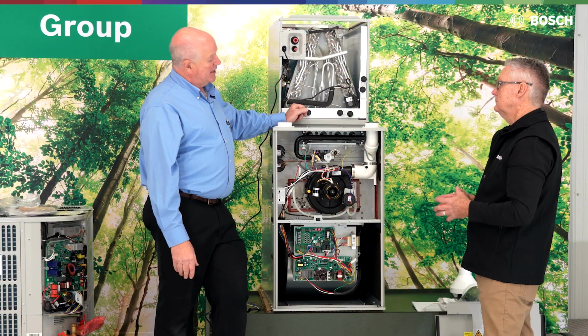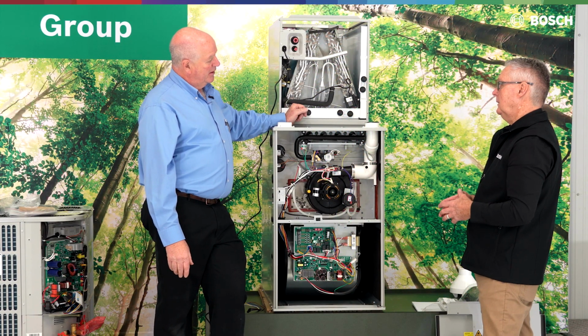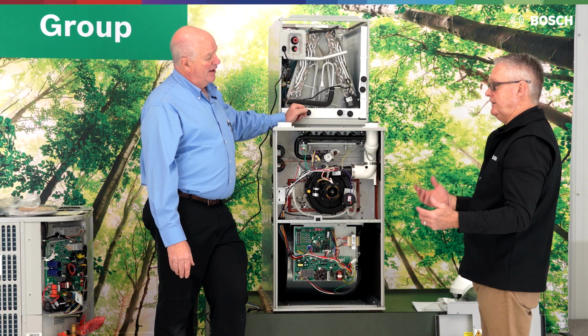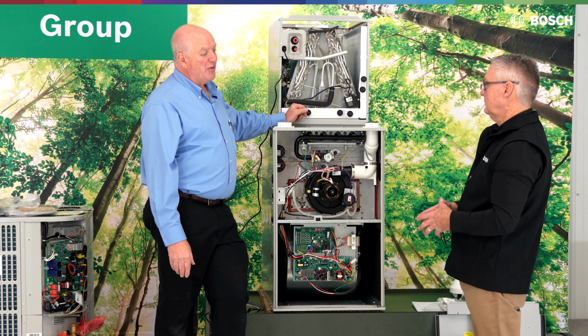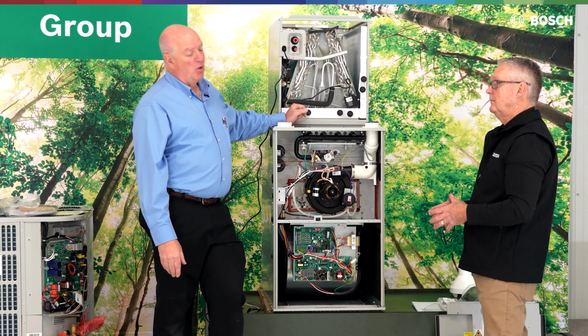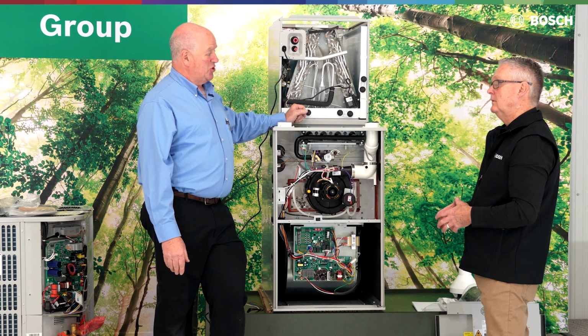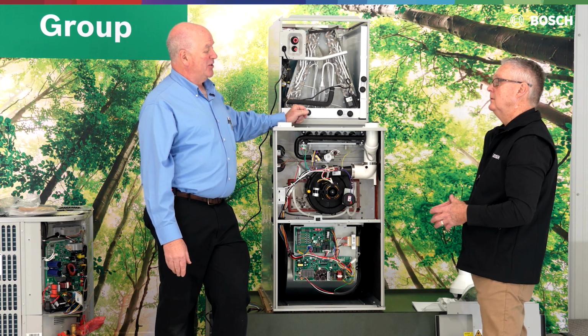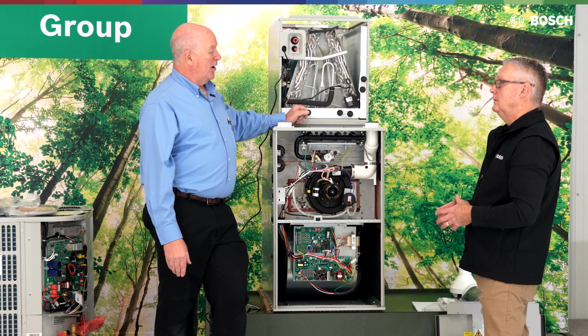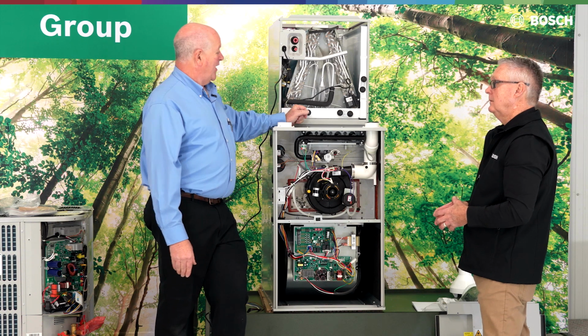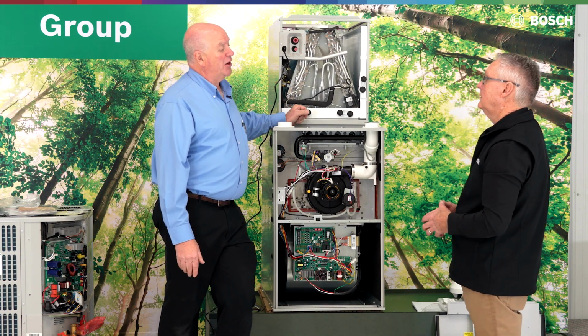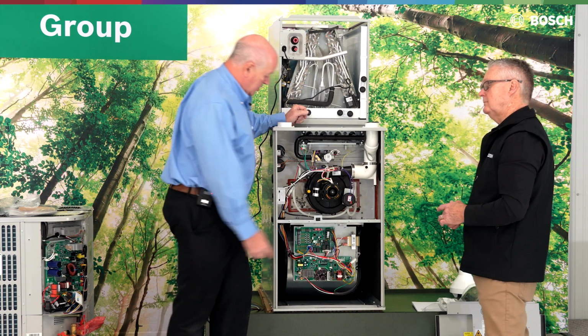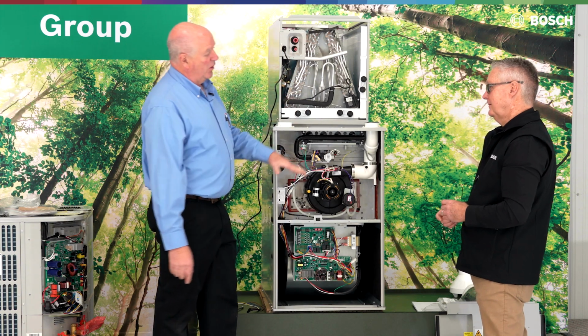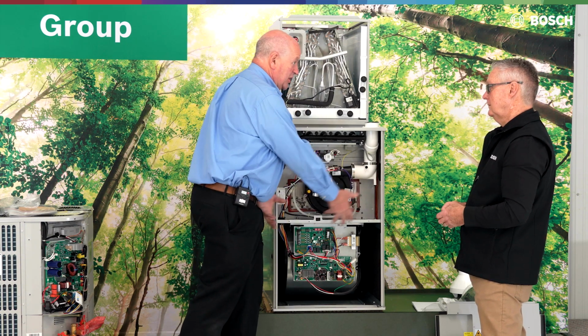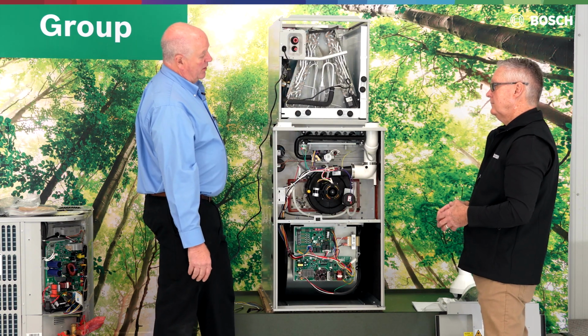And really, if you're cleaning the coil, what does that tell you, Fred? Somebody didn't change the filters, or maybe didn't put the filter in correctly. This has happened sometimes: Mrs. Jones goes to get a filter, she forgets about it, she doesn't find one, and you get a call that we don't have any air conditioning, and you find that she didn't put the filter in for a year. So that'll be an issue with the blower wheel, the coil, the secondary heat exchanger, and now our cased coil, A coil.